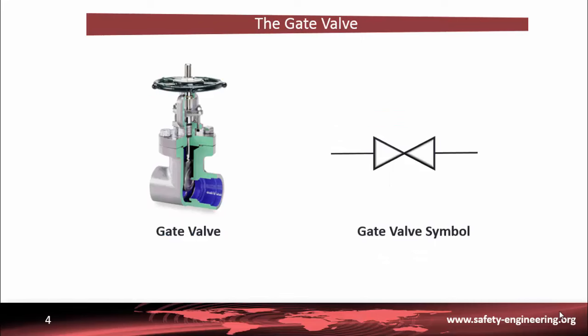The first shut-off valve explained in detail here is the gate valve. The valve is primarily designed to start and stop flow. In service, these valves are generally either fully open or fully closed. The disk of a gate valve is completely removed when the valve is fully open — the disk is fully drawn up into the valve bonnet. This leaves an opening for flow through the valve at the same inside diameter as the pipe system in which the valve is installed. A gate valve can be used for a wide range of liquids and provides a tight seal when closed. The advantages are good shut-off features; gate valves are bidirectional and can be used in two directions, and pressure loss through the valve is minimal. The disadvantages are that they cannot be opened or closed quickly, are not suitable to regulate or throttle flow, and are sensitive to vibration when in an open position.